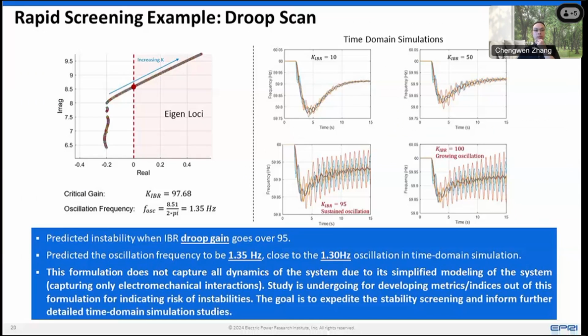The application of the algorithm gives figures like this on the left, showing an eigenloci as you change parameters in the IBRs or system configuration. For example, here I'm showing that as we tweak the droop gain of the IBR providing frequency response, the algorithm tells you that if the gain crosses a certain value—in this case, a droop gain of 98—you can expect oscillations and instability, with an oscillation frequency of about 1.35 hertz.